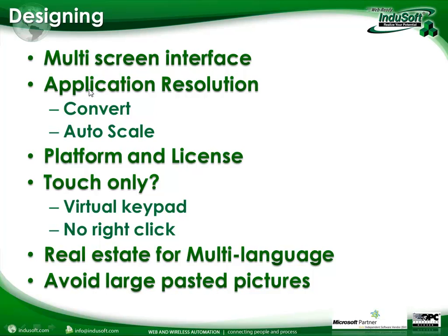It's also a good idea to decide on your application resolution. Are you using a widescreen PC to deploy this on versus a different aspect ratio? A lot of laptops and desktop computers are coming with wide screens, where industrial PCs are still coming with a 4:3 aspect ratio. So you need to take a look at where you're going to deploy this versus where you're going to develop it. There is a convert resolution feature built into the product that works pretty well, and there's also an auto scale feature.